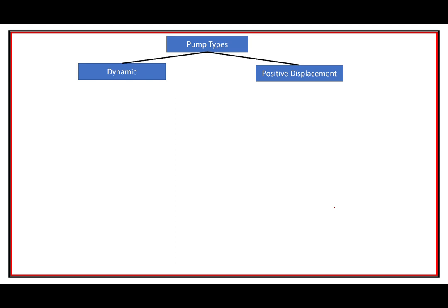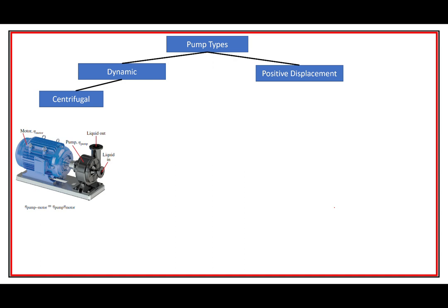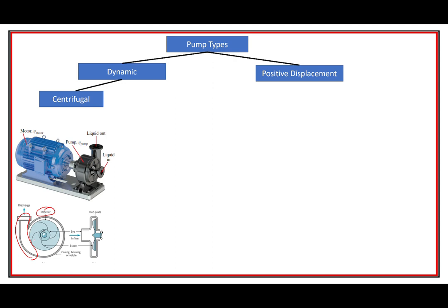I added this section on pump types just for your information. We have two broad categories of pumps: dynamic pumps and positive displacement pumps. Dynamic pumps are what we'll talk about in turbomachinery. Centrifugal pumps are probably the most common - they use an impeller to increase radial velocity, and then that flow gets captured in something called a volute where it gets slowed down and pressure is increased.